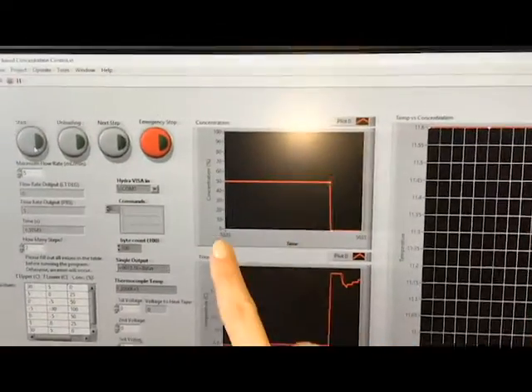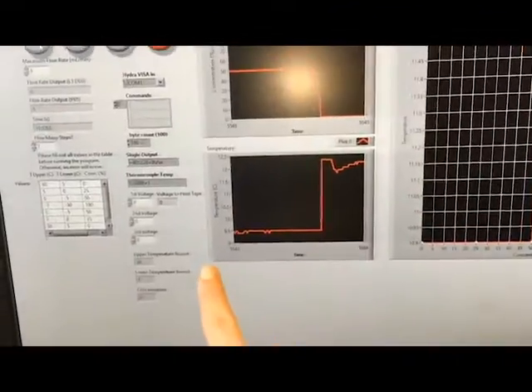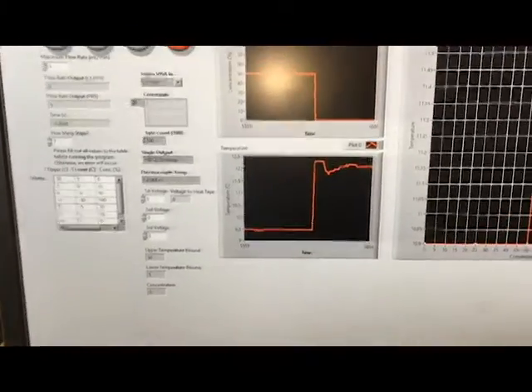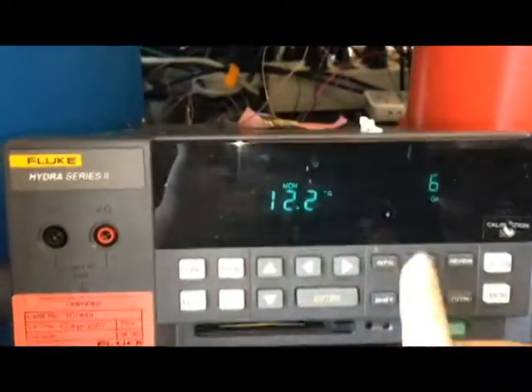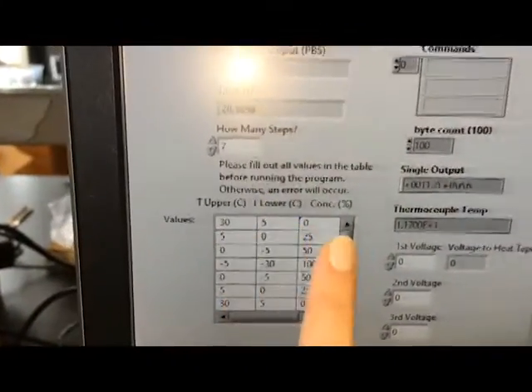You can see the change in the graph switch to the concentration that is being output, which is 0. And this temperature is the thermocouple temperature inside the cell chamber. Here you see that it is 12.2 degrees Celsius, and that 12.2 is perfectly between 30 degrees and 5 degrees. So we have a concentration output of 0%.